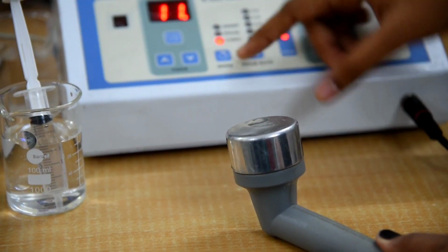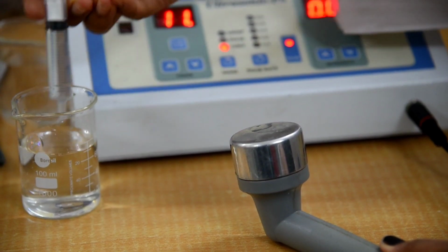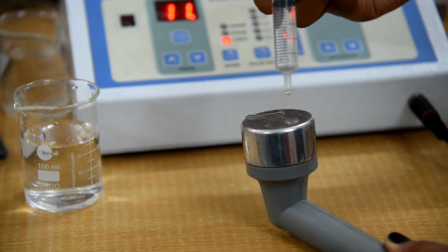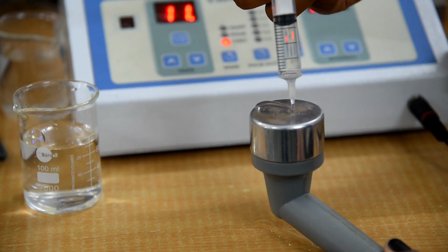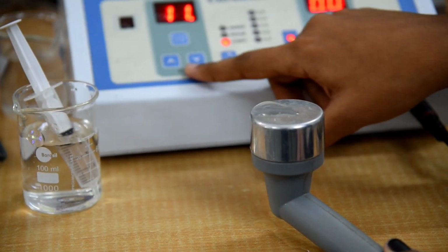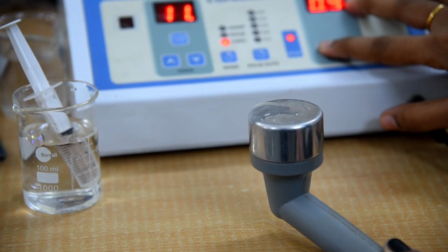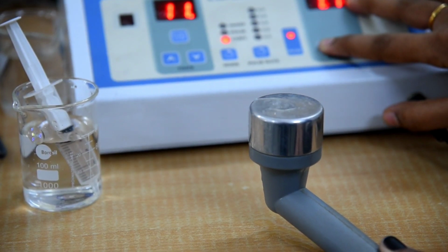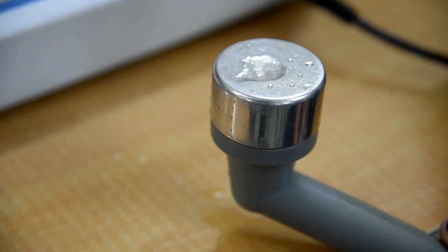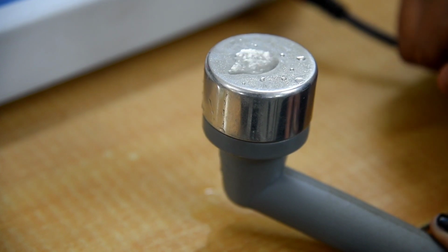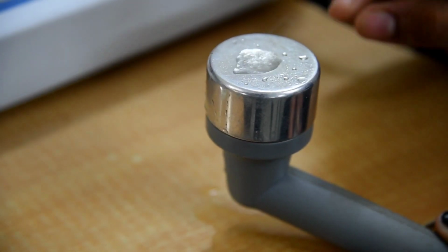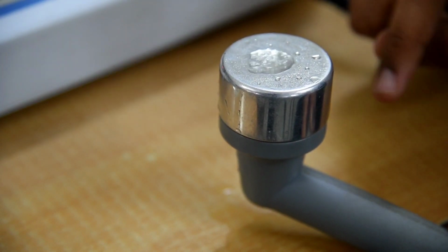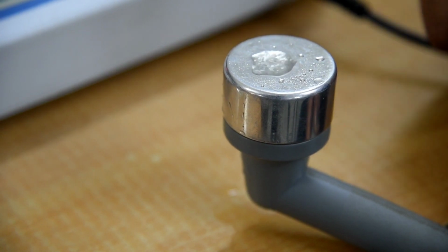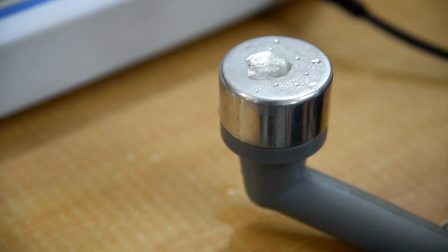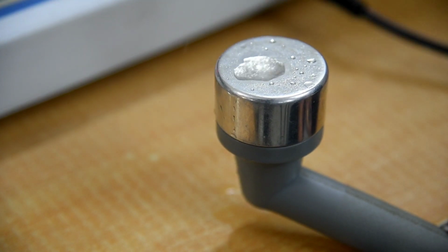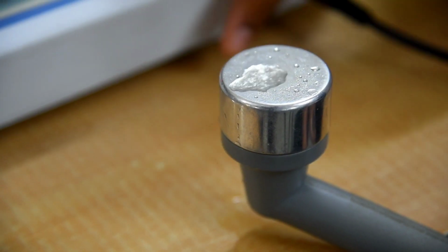In the continuous mode, we take water droplets here to test it. If we set the timer and give the intensity, the water droplets start to vibrate, which indicates the heat energy, and in this way the continuous mode works. This is used in physiotherapy for therapy. And so if we change the mode again, this is pulse mode.